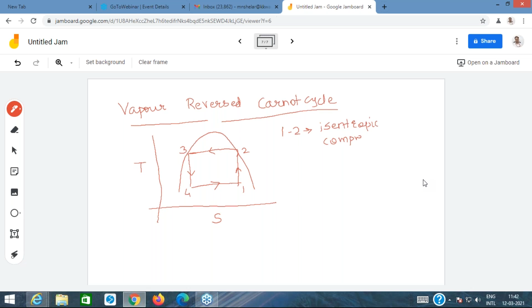So 1 to 2, what is the 1 to 2 process? 1 to 2 is the isentropic compression. If you look at the diagram carefully, the isentropic compression here is a wet compression. And wet compression is many times not at all desirable and not at all feasible, because if the refrigerant is wet at the inlet, especially for most refrigerants, that would create issues with the compressor operation. So the refrigerant should be dry most of the time, or it should be superheated. That is the requirement in most cases. Of why most, we'll discuss later. So the refrigerant should be dry at the inlet of the compressor. This is one of the limitations: if you construct a vapor reverse Carnot cycle, then 1 to 2 is an isentropic compression, which is a wet compression.